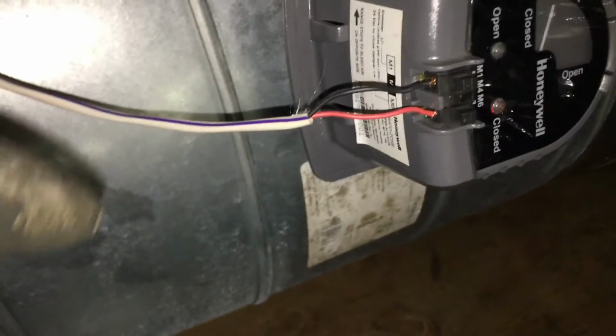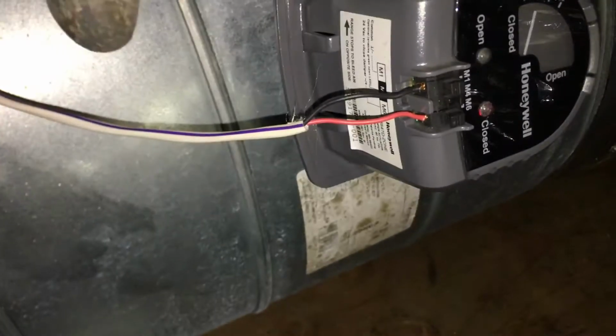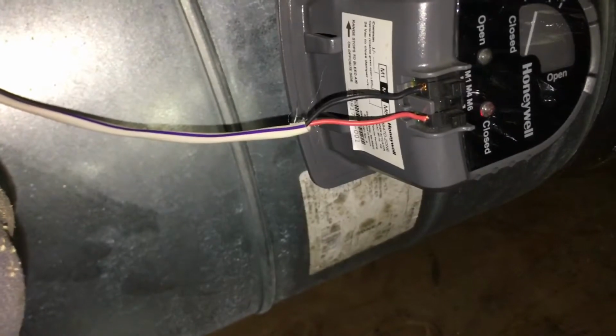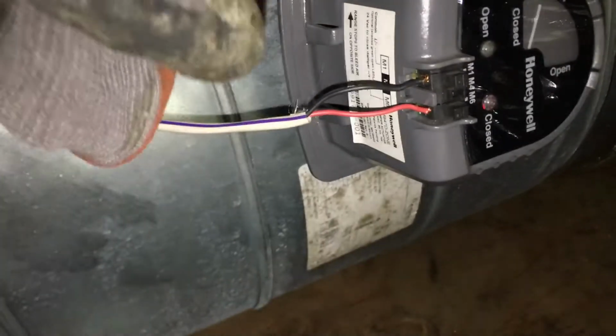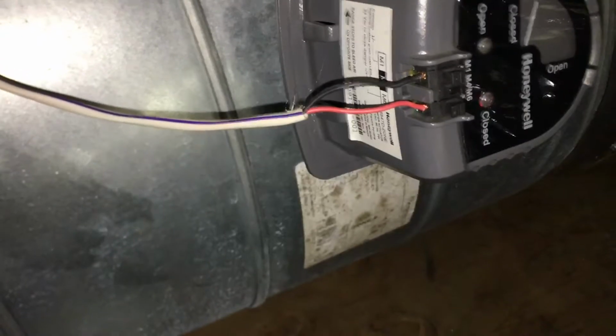It turned out, if you watch the other 2 videos, that upstairs in the package unit, they installed the wrong transformer. They installed a 240 volt to 24 volt transformer, but the power into the AC unit upstairs in the package is 208. So at the transformer upstairs, it was 21 volts with no load, and as soon as you energized any of the dampeners, it dropped down to 19 volts.